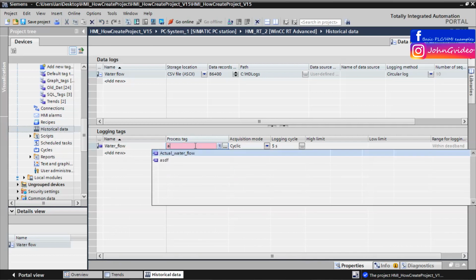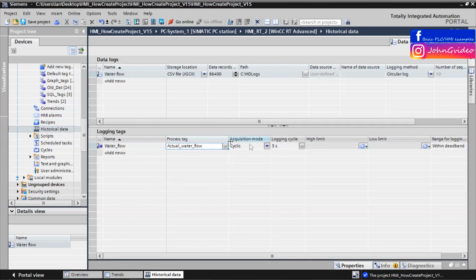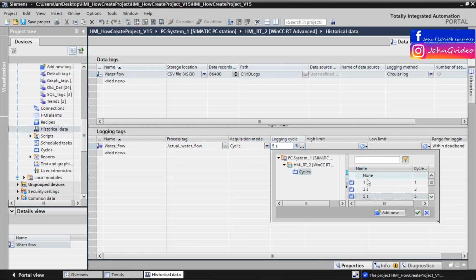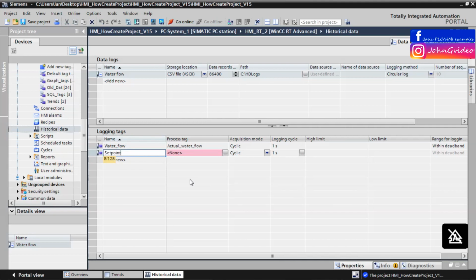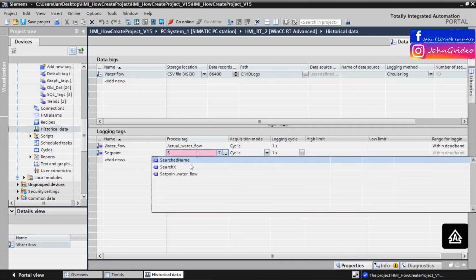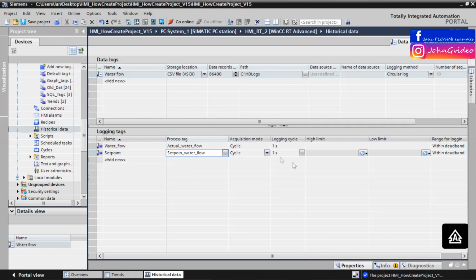We use cyclic acquisition mode and we want to log this tag every 1 second. Second is set point, process tag with name set point water flow, and we have the same options, cyclic acquisition mode and logging cycle. Okay, we save the project. And this is all for data logging.